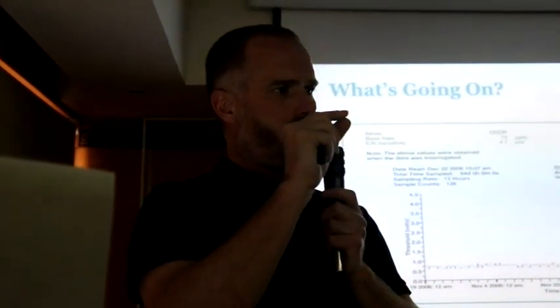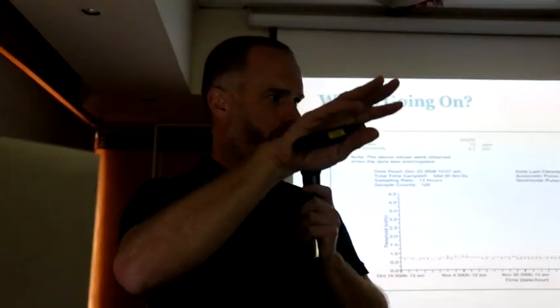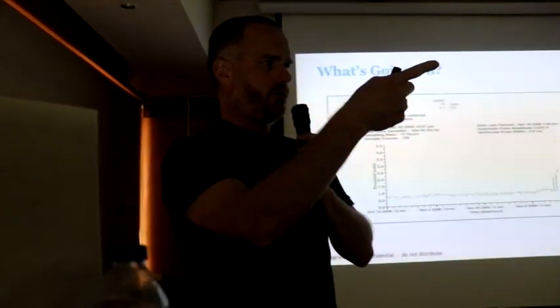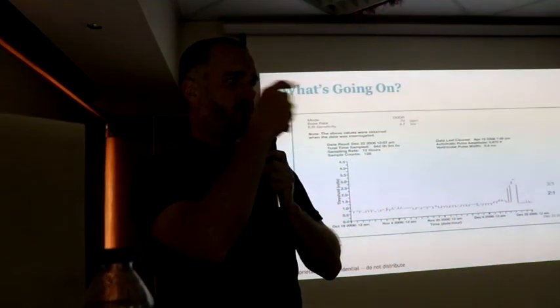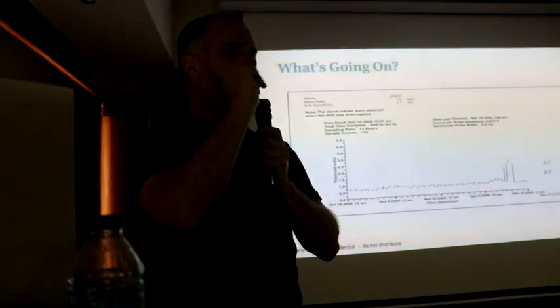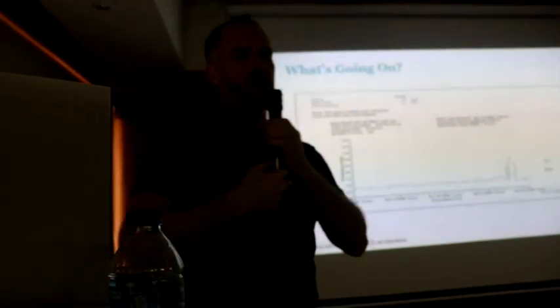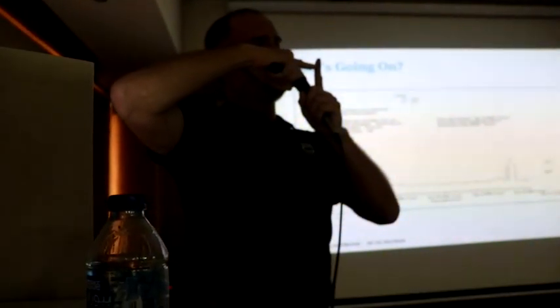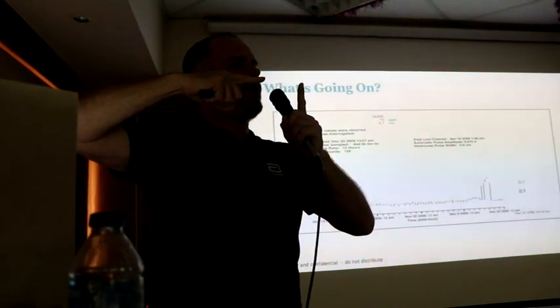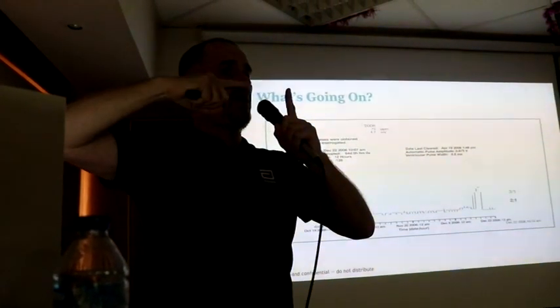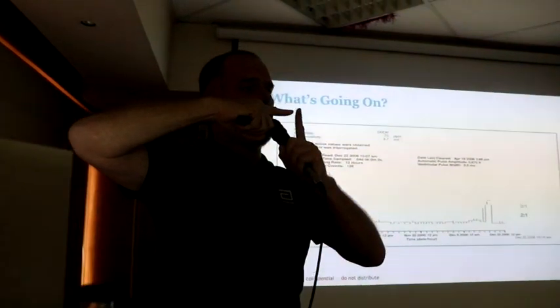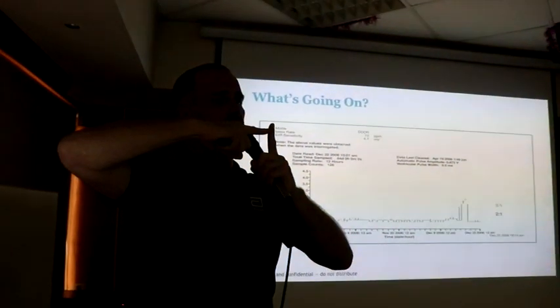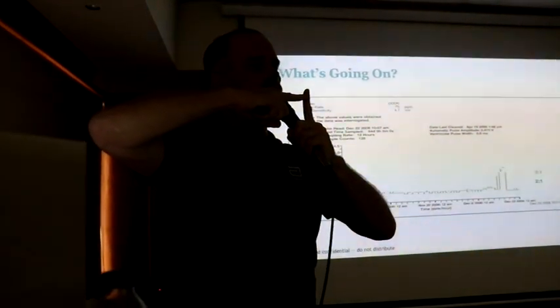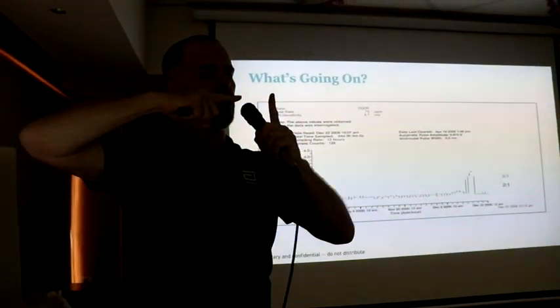What you've got to remember is that there's no more steroid on that lead. So you put it into the muscle, no steroids coming. Some doctors will give the patient some oral steroid, if it's okay, because when you put the lead in, you get inflammation at the lead tip, which pushes the lead back, further away from the myocardium. Obviously not this far, but it comes back, and then as the swelling comes down, it moves back in again. If you have steroid, it does this, and then it comes back. If you have no steroid, it does this, and it only comes back a little bit.